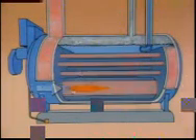During operation, water enters through the feed water line. The water level is maintained above the fire tubes to protect the tubes from overheating. Fuel and air enter the combustion area. The burning fuel transfers heat to the water in the shell. The hot gases flow through the fire tubes, and additional heat is transferred to the water surrounding them. Each time the gases are routed through the shell, it's called a pass. The gases pass through 2 times in this example, so it's a 2-pass boiler. The combustion gases flow out of the boiler here in this example.